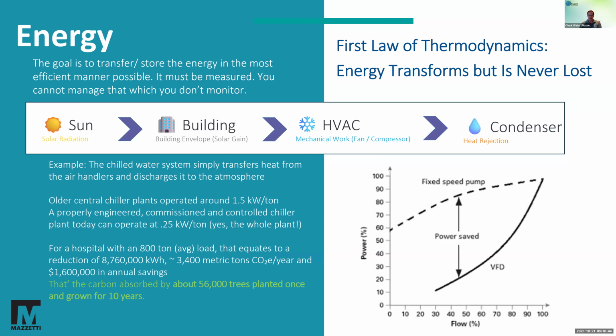Now, you can't just go to your VFDs and park them all at 80% effectively. Again, there are affinity laws, pump curves, and other things you need to look at, and I certainly recommend you consult with your engineer. But one of the things we do when designing these systems is utilize variable frequency drives and other forms of efficiency to keep the systems operating in their optimal band.